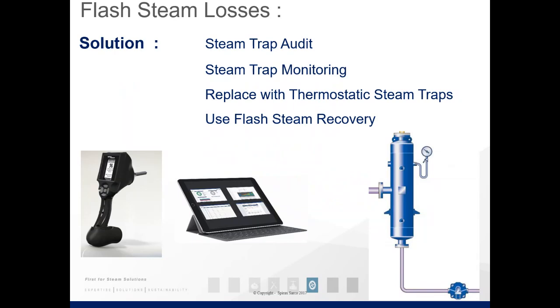So solutions. As I mentioned here, we and other companies, but Spirax, so I talk from our point of view, can do a steam trap audit. So we can tell you if your traps have failed open, failed closed. Steam trap monitoring, so you can monitor these traps yourselves. The moment you have a fault or a challenge in your system, it can tell you, and then you can do the relevant servicing. Replace with thermostatic steam traps. Again, that's more for main lines, and use flash steam recovery. This item here on the side, you would put into your condensate system. It's designed to recapture the flash steam from the differential pressure and take that to a process that you can use.